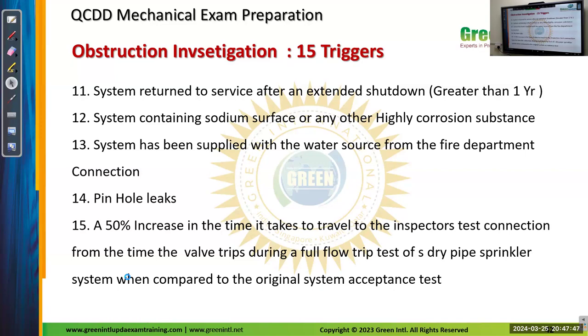A 50% increase in the time it takes to travel to the inspector's test connection. That is a test train, right? So from the time the valve trips during a full flow trip test condition, dry pipe sprinkler systems when compared to the original system acceptance test. Means in dry pipe conditions, there will not be any water present in that.